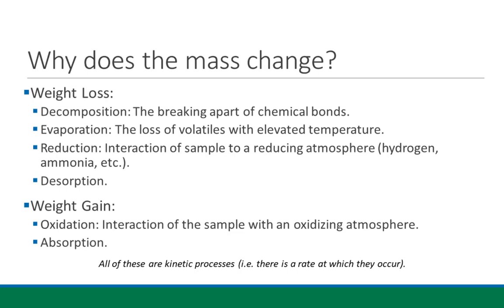Evaporation refers to liquids or anything volatile at an elevated temperature. If you subject your sample to a reducing environment such as hydrogen or ammonia, then you would see a weight loss related to reduction. Desorption occurs if you had a gas or something adsorbed into your material — something very porous might have this happen. The molecules at elevated temperature will have enough energy to escape that pore structure and you'll see the mass loss.